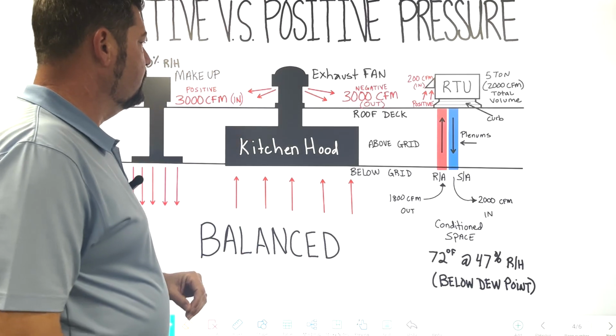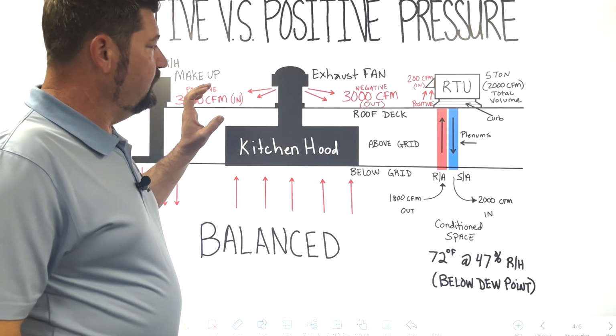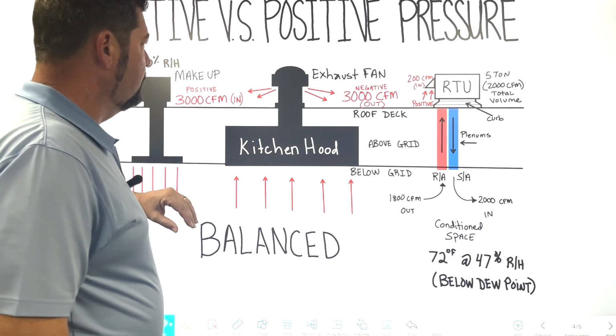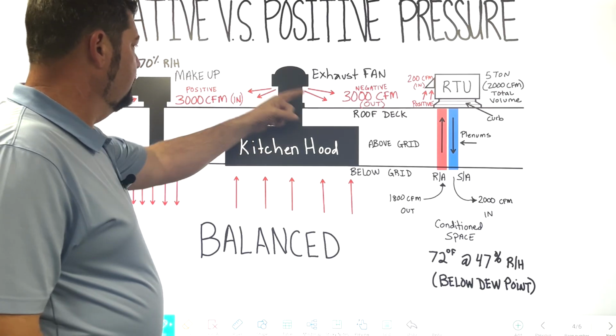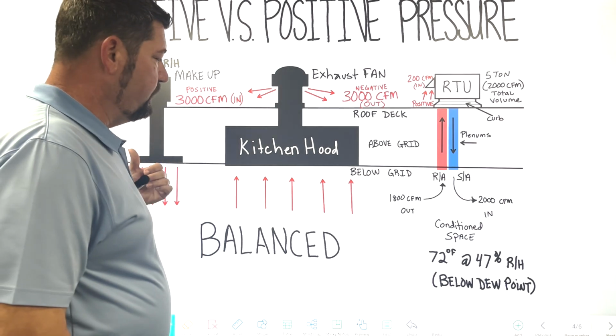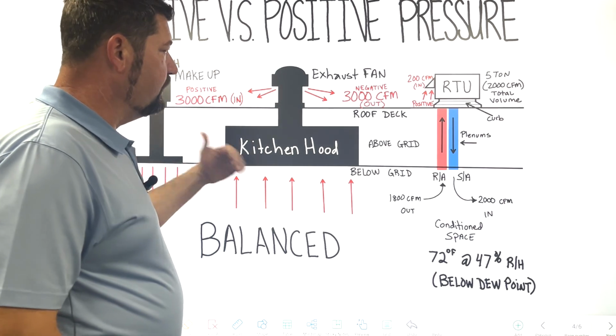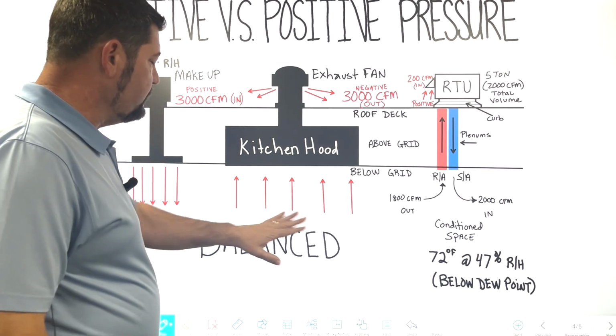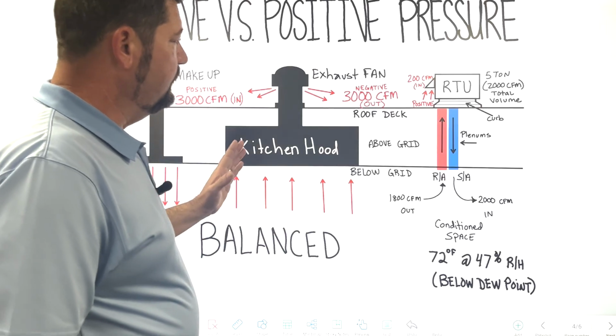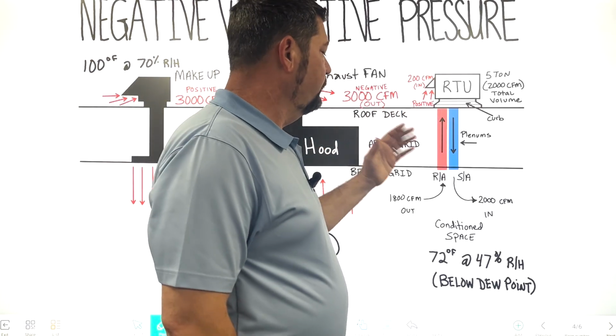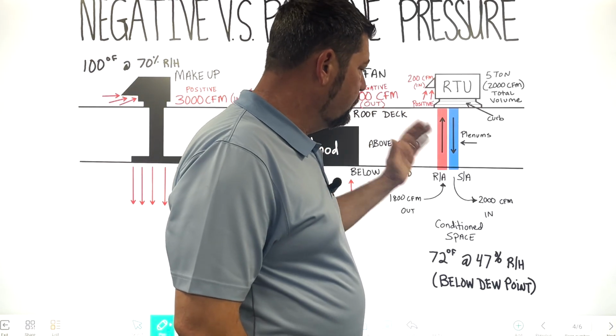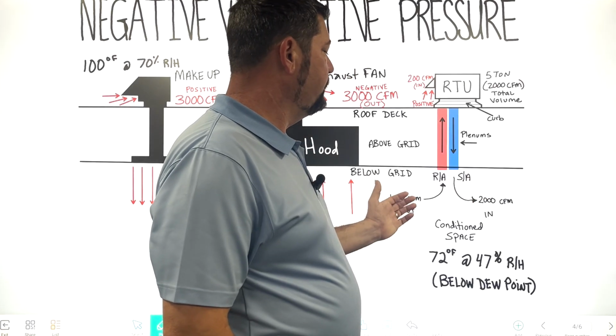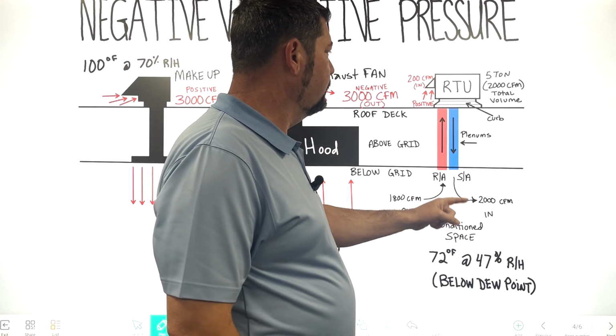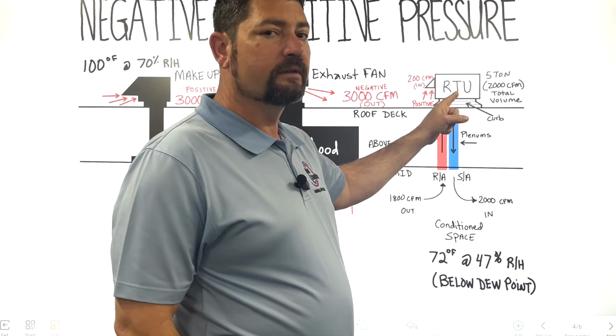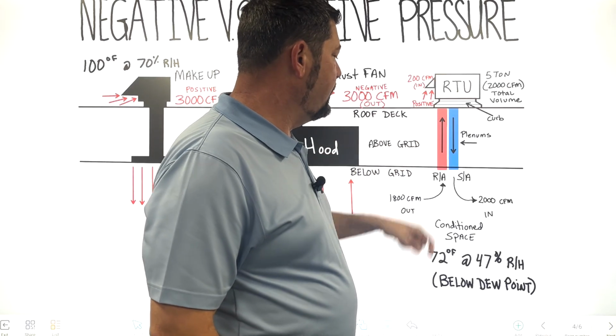Your kitchen hood is not in the same sync as your makeup, and you have a difference in CFM. So we are creating too much positive pressure or too much negative pressure. It has to be 100% balanced. And then over here, your RTUs, you have got to be bringing in more CFMs than you're taking out of the building. And the only way to do that, since the motor doesn't give you a difference, is to add some outside air to it.